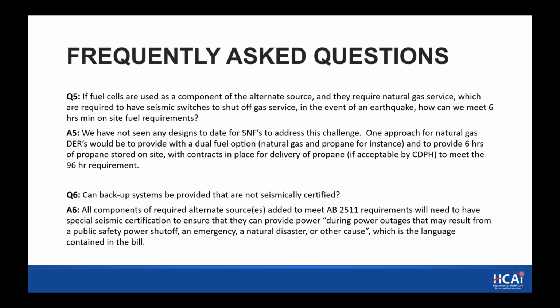Question 5. If fuel cells are used as a component of the alternate source and they require natural gas service, which are required to have seismic switches to shut off gas service in the event of an earthquake, how can we meet 6 hours minimum on-site fuel requirements? The answer: we haven't seen any designs to date to address this challenge. One approach for natural gas distributed energy resources would be to provide the unit with a dual fuel option, for instance natural gas and propane, and to provide 6 hours of propane stored on site with contracts in place for delivery of propane, if it's acceptable by CDPH to meet the 96-hour requirement.